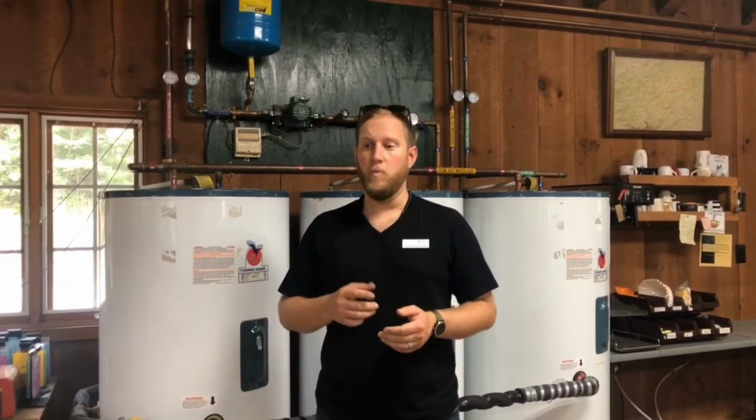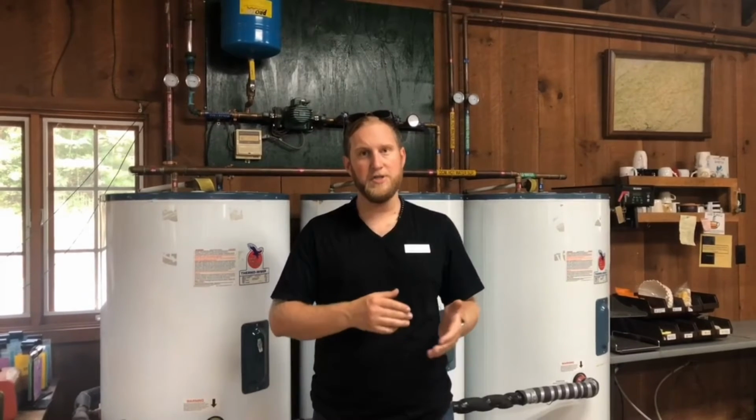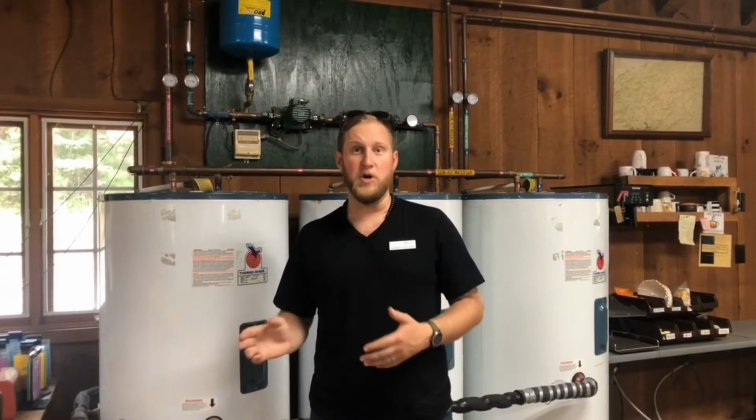So the maintenance is fairly straightforward. There aren't a lot of moving parts with a solar hot water system. Once a year, we'll have someone come in and make sure that our glycol levels are correct and they might recharge the system. Other than that, as long as it doesn't give us an error message, it's kind of set in on its own. I would recommend a drain back system and make sure that it's a closed loop system just for efficiency's sake, but really it's pretty minimal.